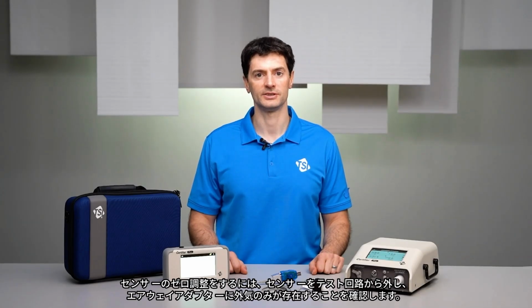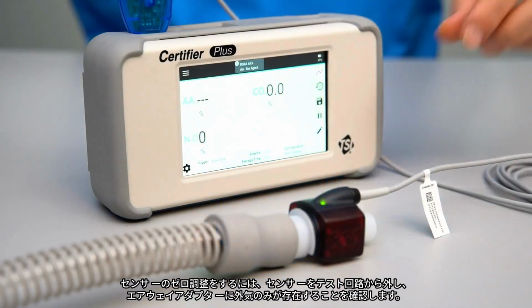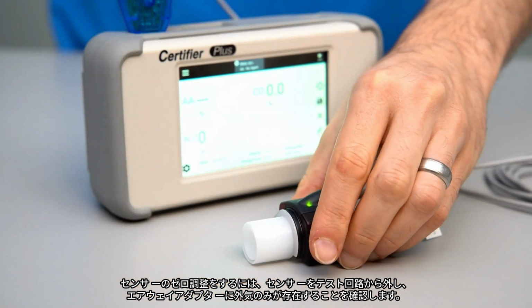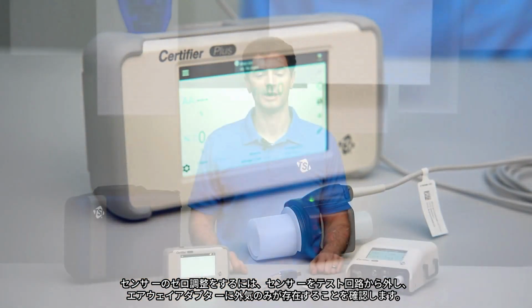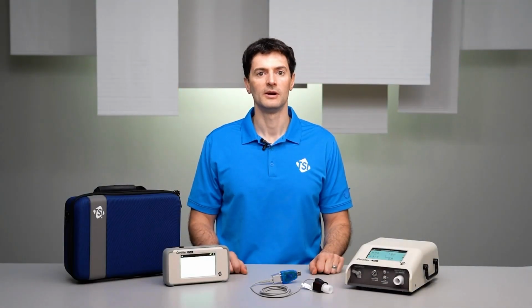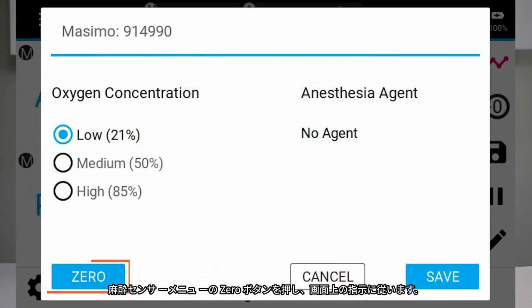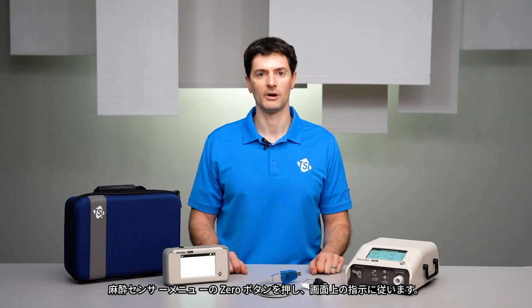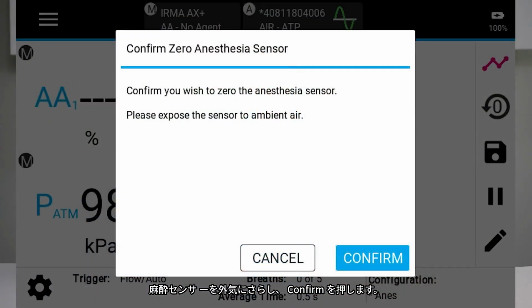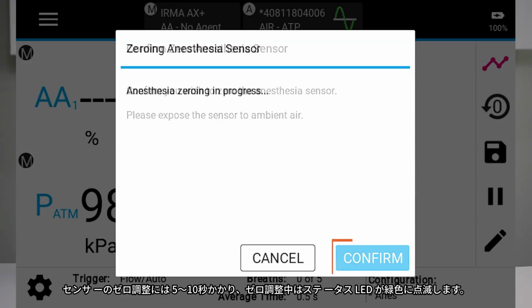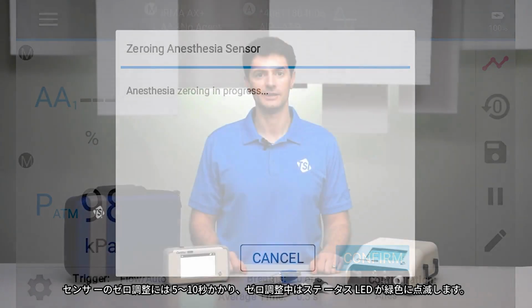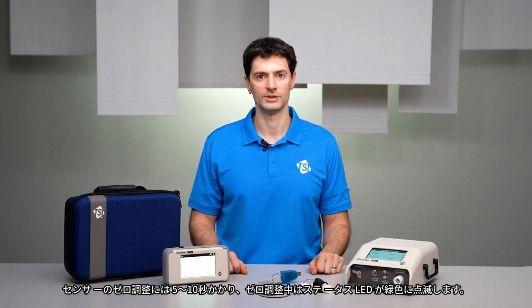To zero the sensor, disconnect it from the test circuit and ensure that only ambient air is present in the airway adapter. Press the 0 button in the anesthesia sensor menu and follow the on-screen prompts. Expose the anesthesia sensor to ambient air and press confirm.